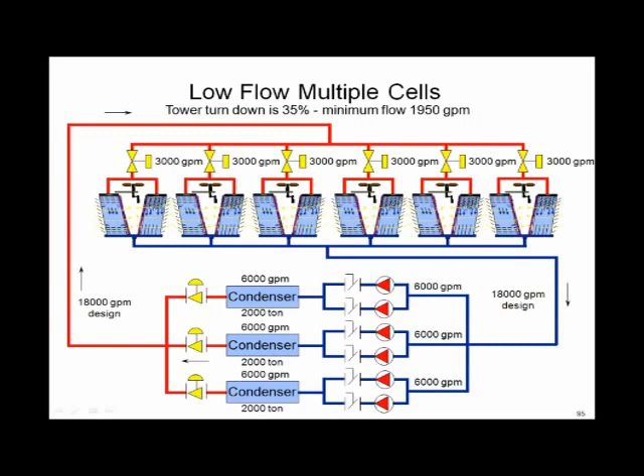So if you're specifying ASHRAE 90.1 2010 on cooling towers, they've got to be able to turn themselves down flow-wise to 50% of design capacity, not having any troubles. Well, the old towers would not necessarily do that. In fact, the vast majority would not do that. So here's the situation. A good friend of mine, by the way, his last name is Leak. I don't hold that against him, but a guy selling pumps named Leak. It's kind of funny to me, but that's what he does for a living.